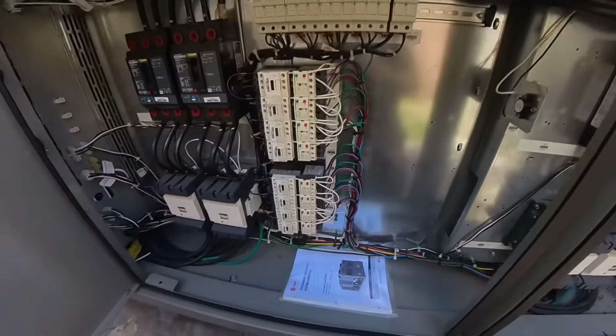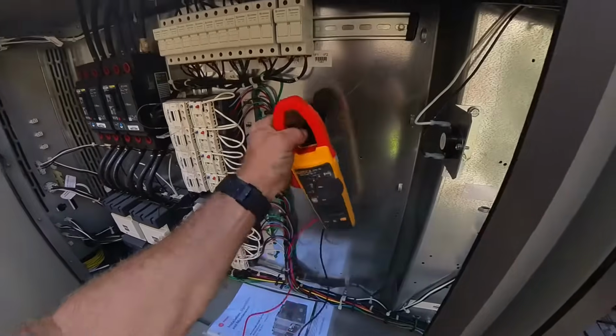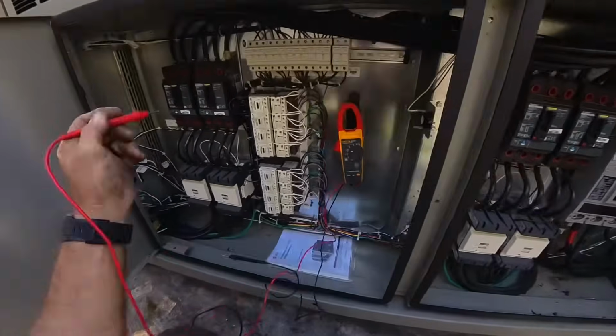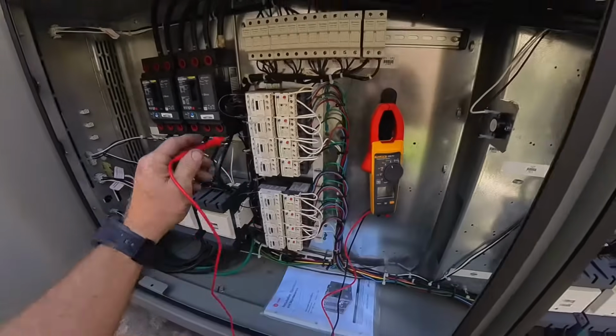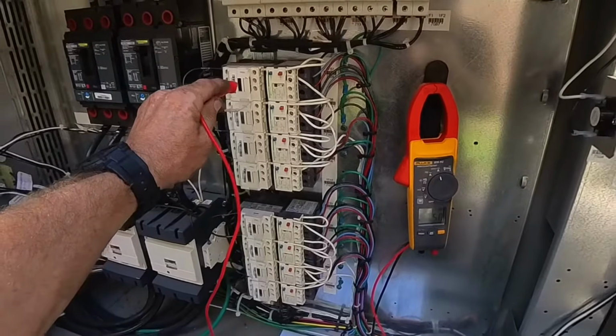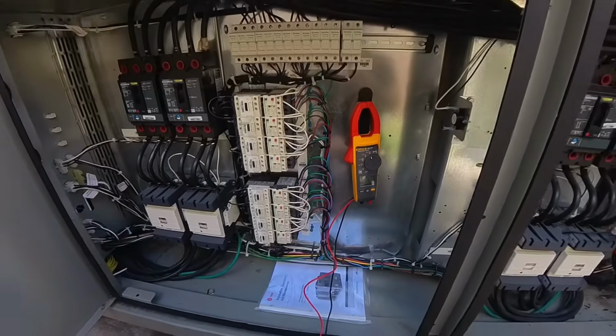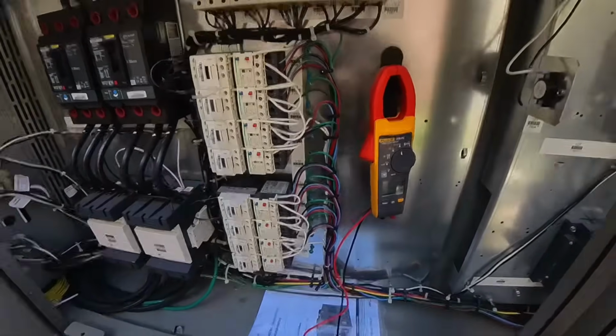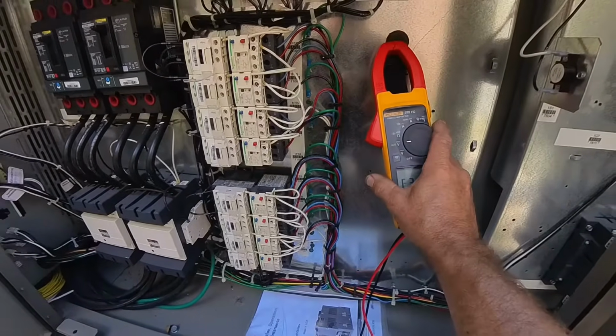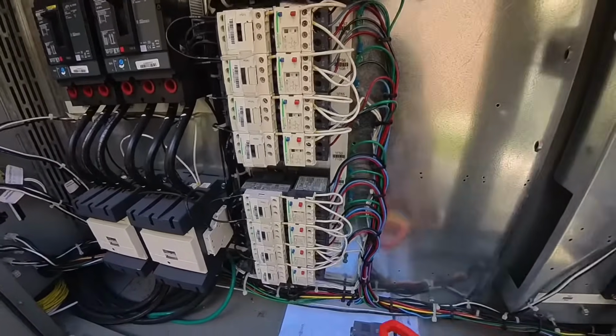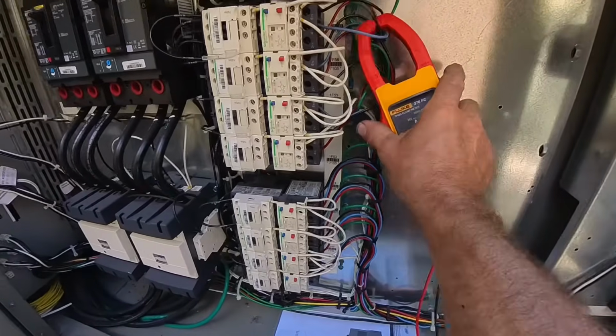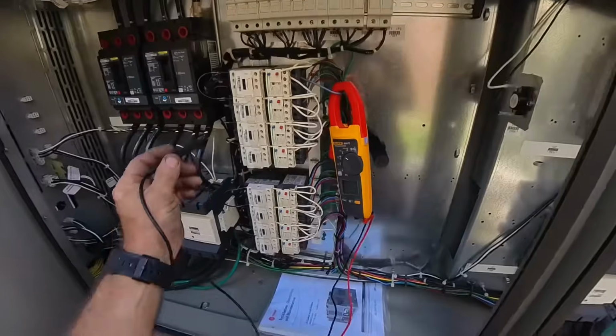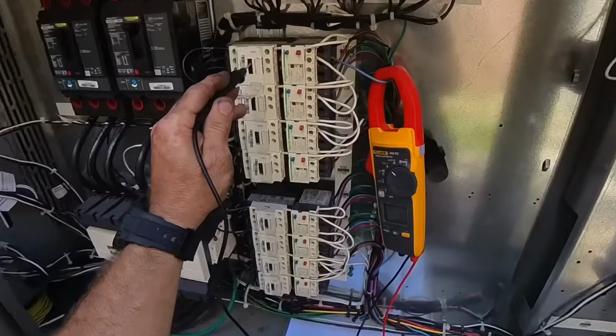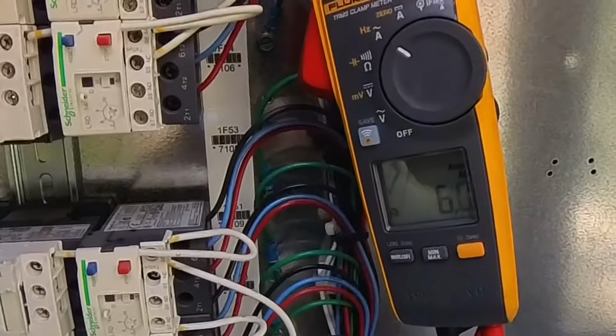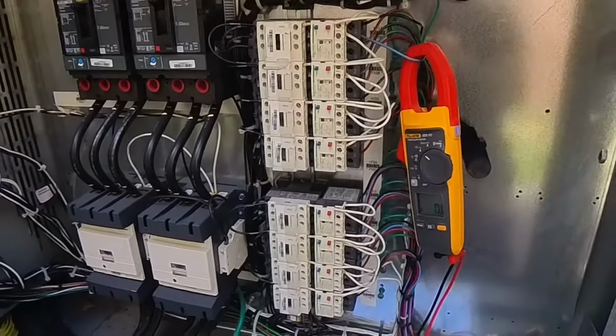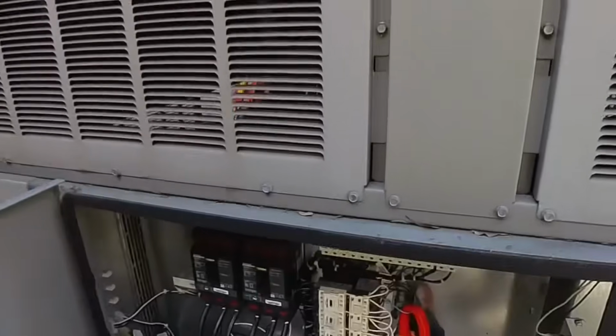Alright, so I got the power back on, that shroud is back on. I'm just going to bump this fan starter. It's not set to come on, so hey, let's see what happens. It's either going to blow or it's not. She's spinning. Let's check our amp draw on that thing. Doesn't sound the best, but it's working. Let's go check it.